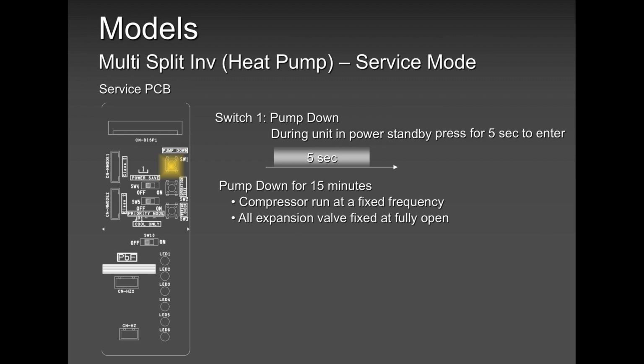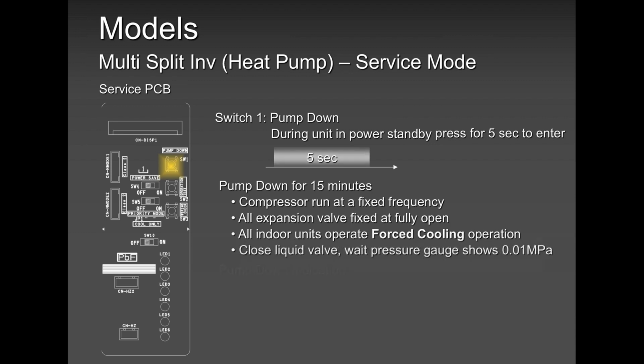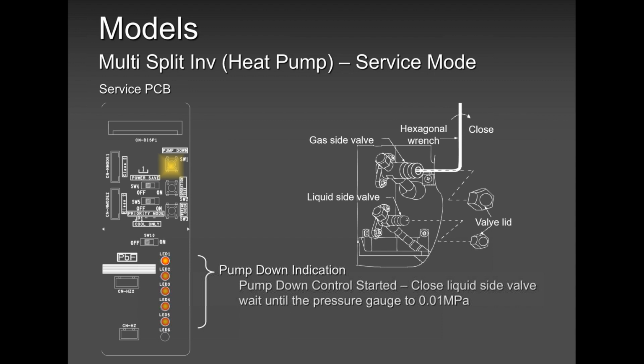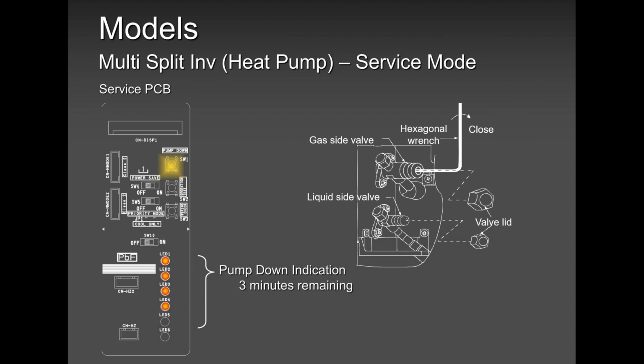All the electronic expansion valves are fully open. The indoor units are forced to be in cool mode. Even if they were in heat mode, they will switch over to cool mode. All the gas will be collected to the indoor unit, sorry, to the outdoor unit. And as you are watching the gauge, you are watching the lights. The lights will tell you 3 minutes left, 2 minutes left, 1 minute left, and you're done.